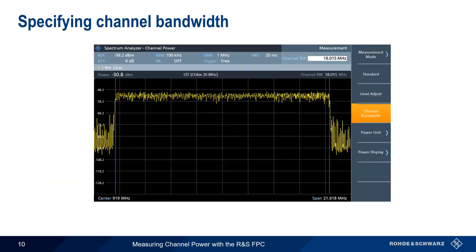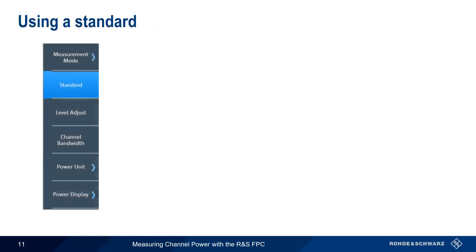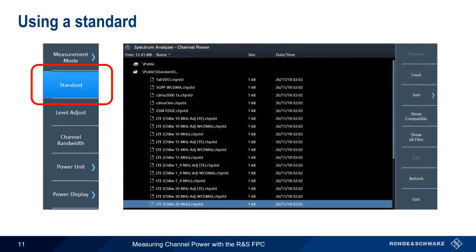In order to measure channel power, we need to specify the width of the channel. This can be done in two ways. The first is by manually entering the channel bandwidth. Another way to specify channel width is using a standard. Recall that channel power is frequently used for measuring wireless communication signals, and the standards for these technologies define nominal channel widths. After clicking on Standard, we can choose from a wide variety of predefined channels. Just select the Technology Type and Channel Width, if applicable, and then click Load. The analyzer will then automatically configure the proper channel bandwidth.